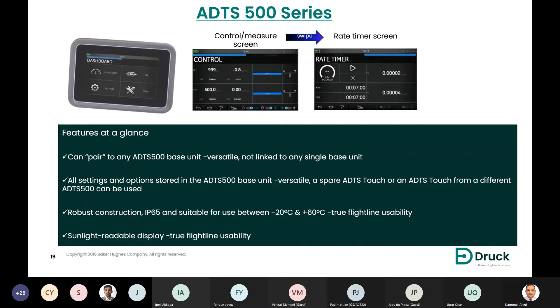The first product is the ADTS 542, which is the ideal solution for light aircrafts, turboprops, helicopters, crop sprayers, air ambulances, police, coast guards, etc. It's a very handy unit: small, portable, self-contained, and you can carry it wherever you want. The device has an ambient operating temperature between 0 and 50 degrees, because it has pumps inside, and you don't want any ice formation inside the device.